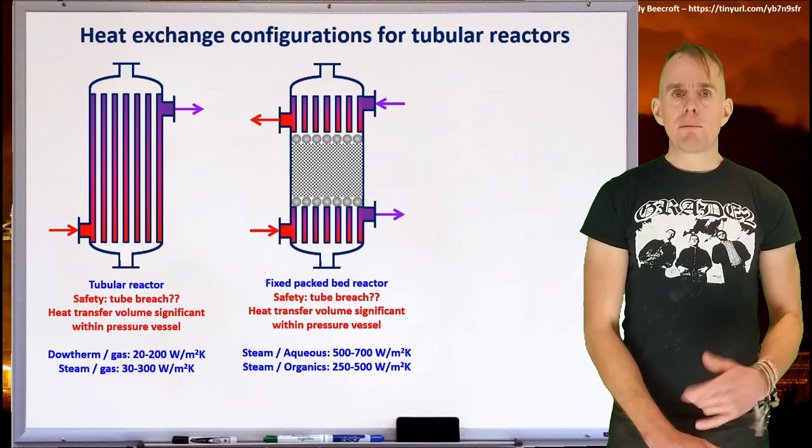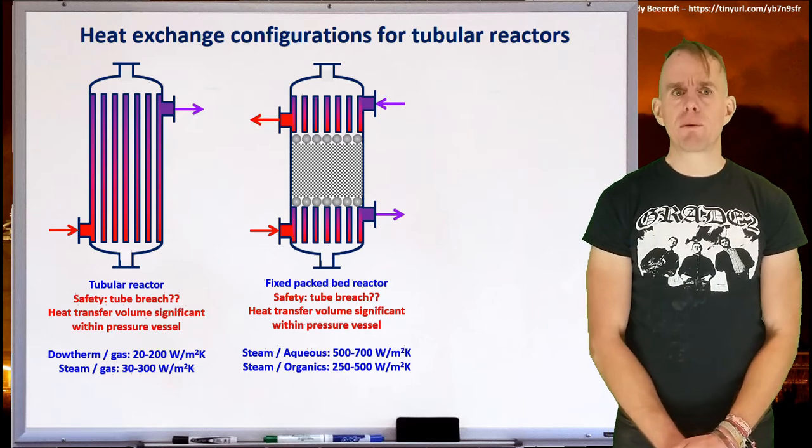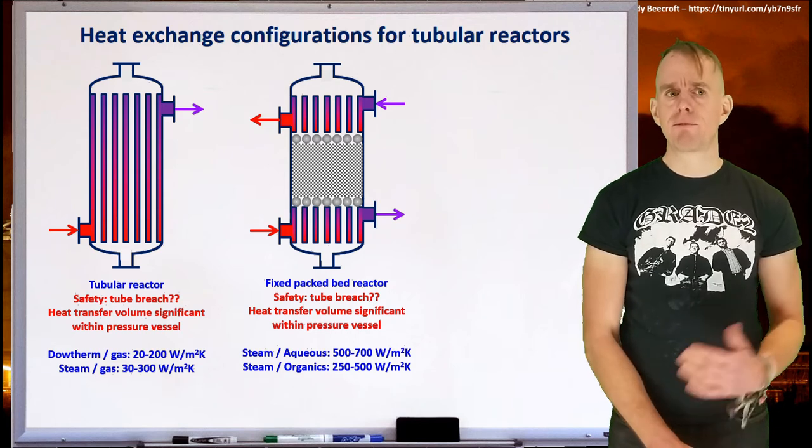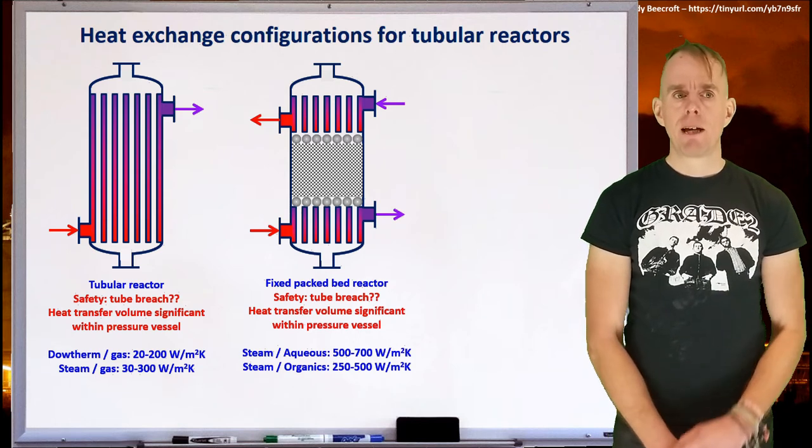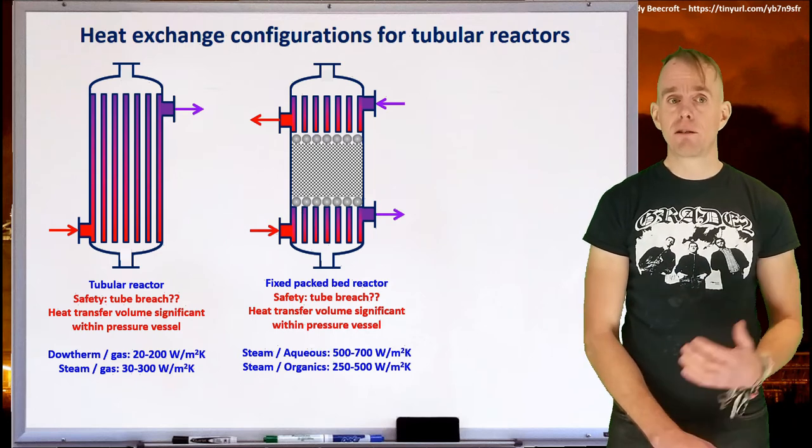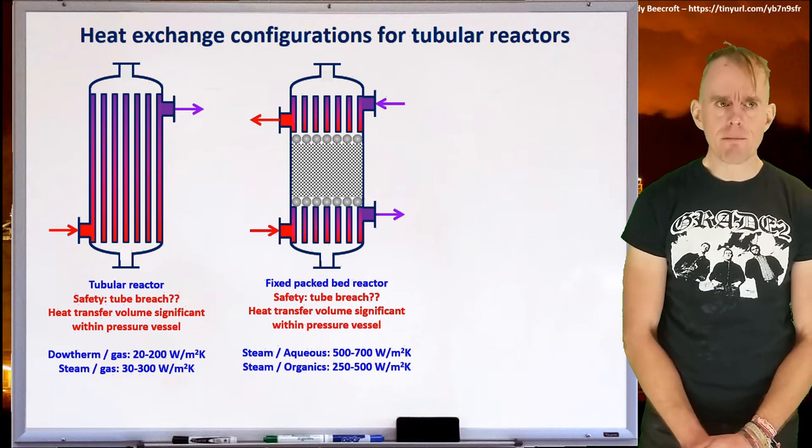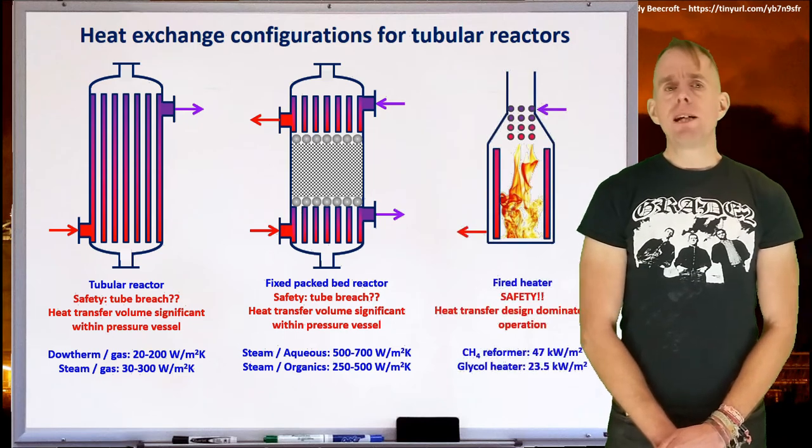So if we think about heat transfer coefficients, if you're using steam with an aqueous mixture, you might get 500 to 700 watt per square meter Kelvin. If you're using steam, heating or cooling organics, you might get 250 to 500 watt per square meter Kelvin. Okay, if we need high temperatures, then we said we need to go down the route of a fired heater or furnace.